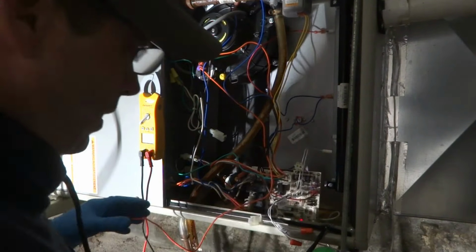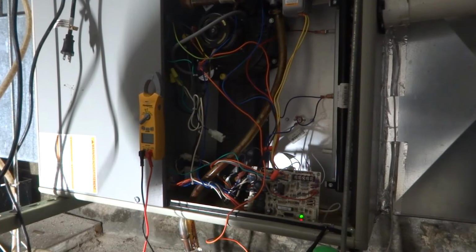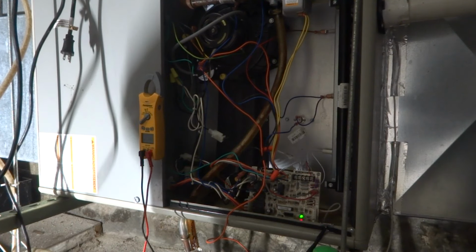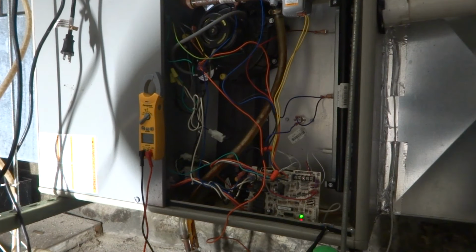This is not our problem. Our problem is that bottom switch has got bad connectors on it. We're gonna do something about that. Put some new connectors on there, at least this one connector. We'll put a new one on there and try it. It's dark and dingy down here. Put a new connector on there and see if we can get power through that switch. It's not going to work unless we can get power through it. Does that make sense? Yeah.